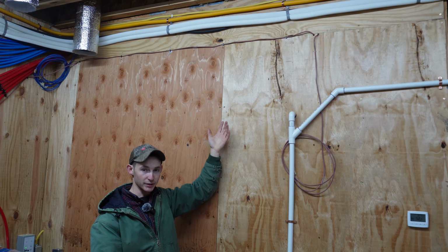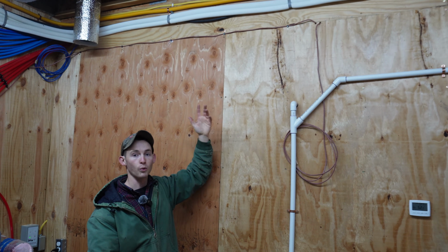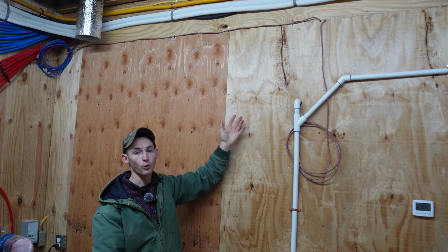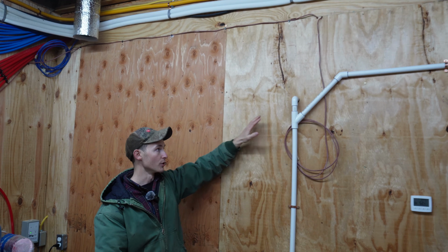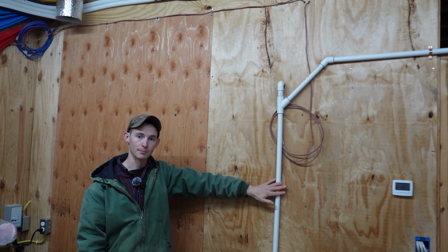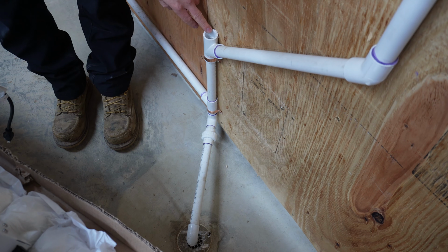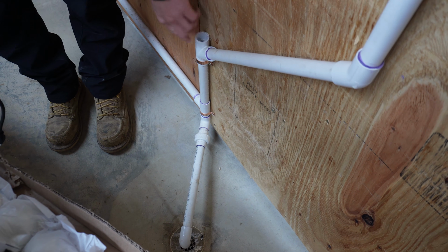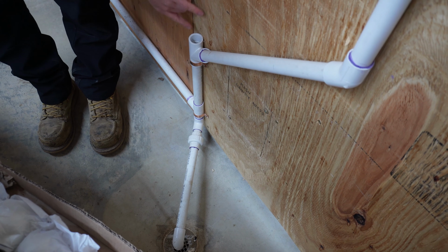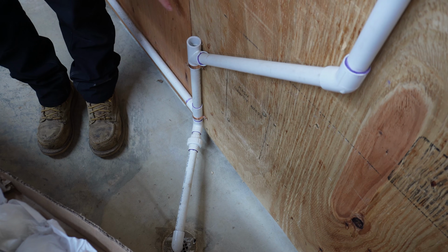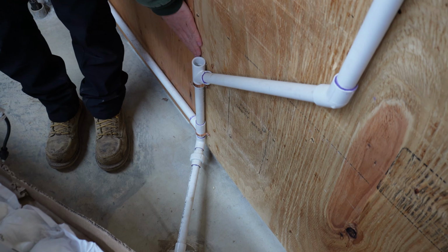Another critical part of dehumidifiers is that they pull water out of the air, and that water needs a place to drain. These are our condensate drains coming from our mini split. Thinking ahead to this dehumidifier install, I put a Y here so I can add to this drain. I'm going to put another Y so I can have a clean-out on top, and the dehumidifier drain will connect right here.